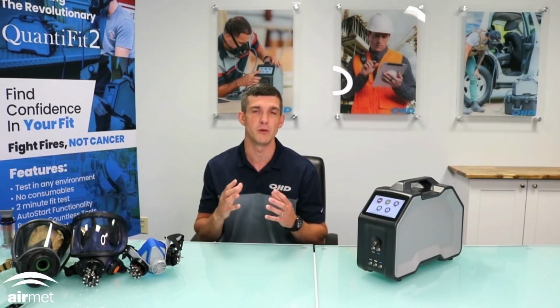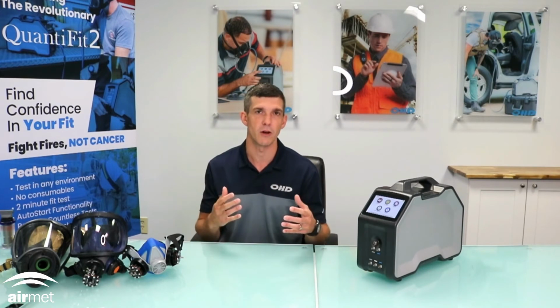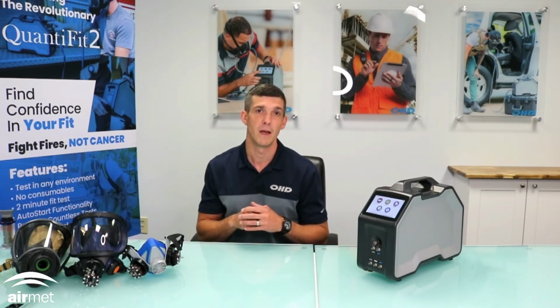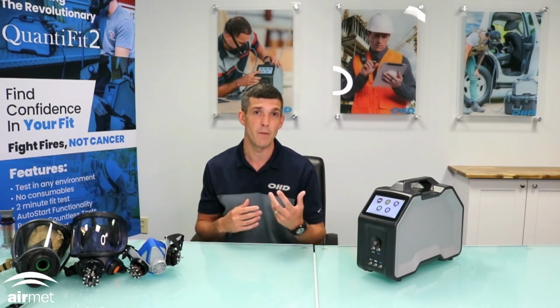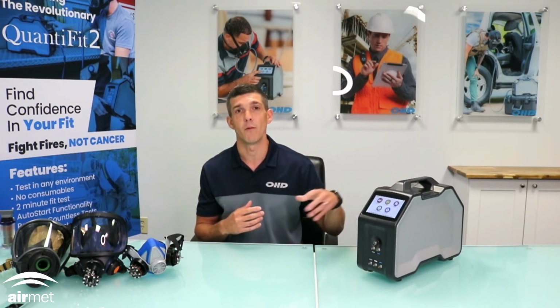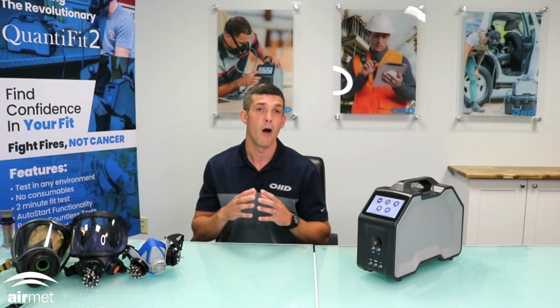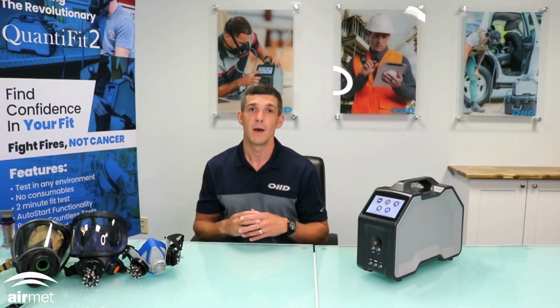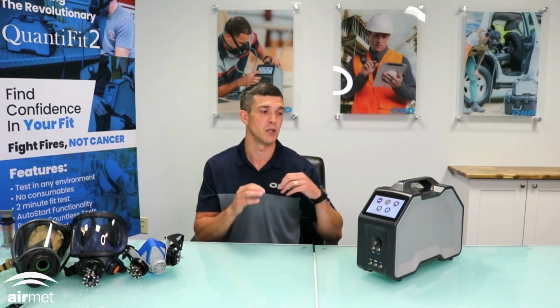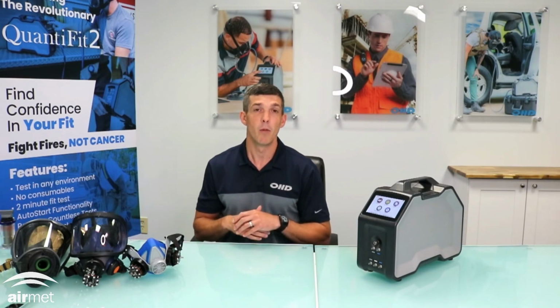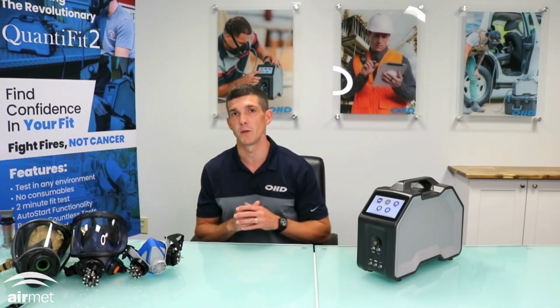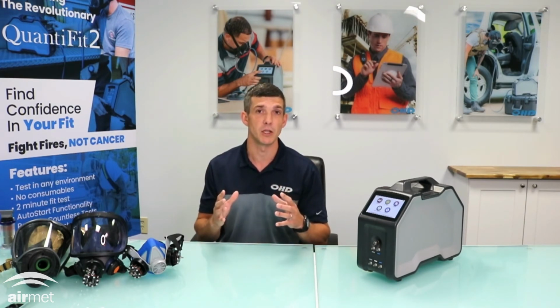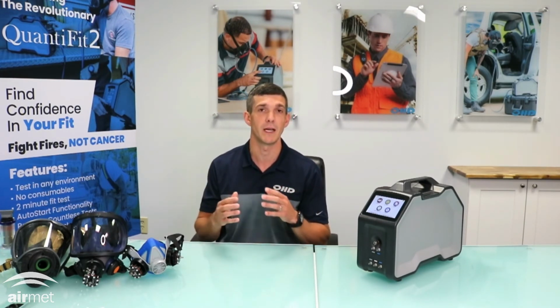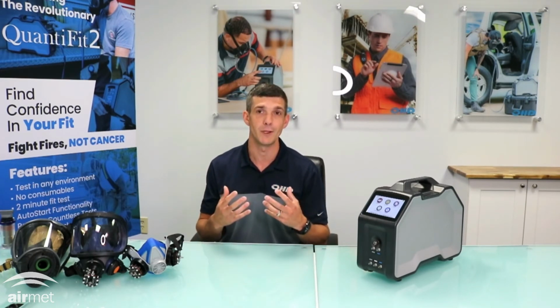The first thing is we've removed any type of trigger button or start button on the unit itself. We use an auto start feature that allows the user to take a breath and hold it, and the machine automatically starts the test without any interaction with the instrument itself. The next feature that I mentioned earlier is the battery power. The unit comes with an optional battery where you can run up to 4 hours of runtime without recharging that battery. Multiple batteries can be charged outside of the unit, so you can just plug and play straight off of that recharge. Perform multiple tests simultaneously. The unit itself comes with Bluetooth on board, so through our OHD Logic software you can run 4, 5, 6 units simultaneously, or as many as you have operators to adequately run.